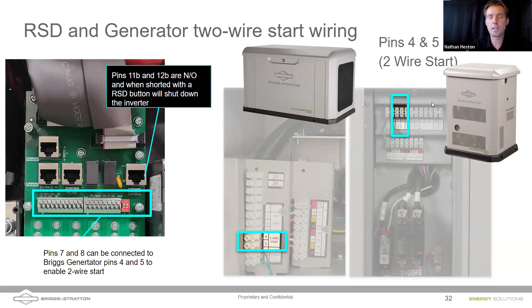So showing you how to do that, Daniel's taken pictures of our 26K and our 13K Power Protect line to show you where those wires go in there. Again, you do have to disable that auto main sensing and use 2-wire start. This is directly out of the Sol-Ark manual. It's showing you what that communications wiring is.